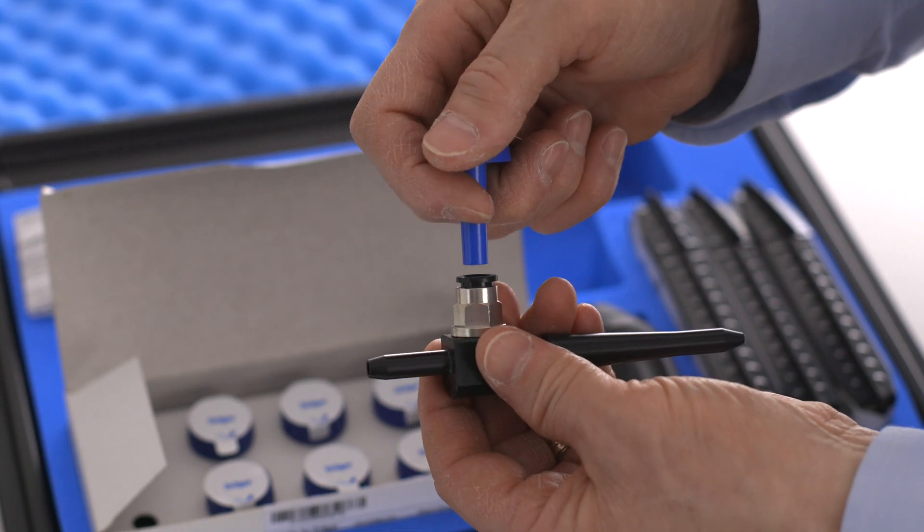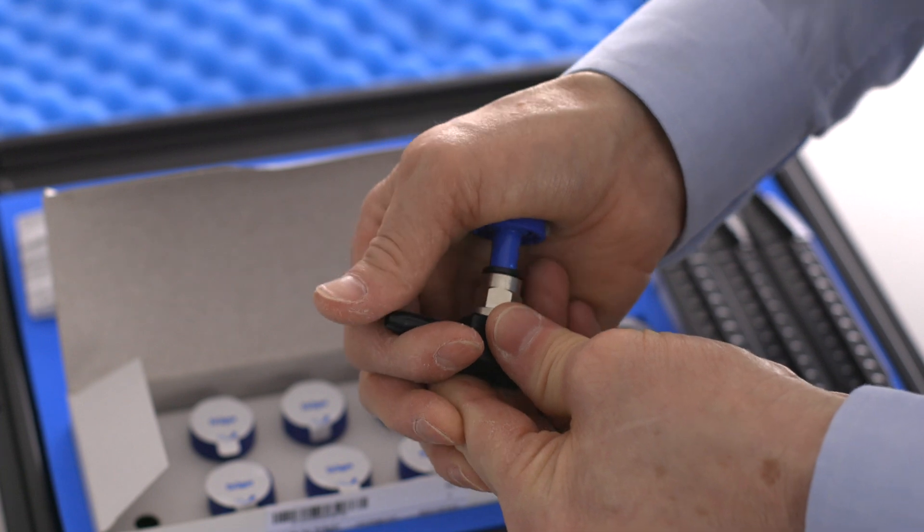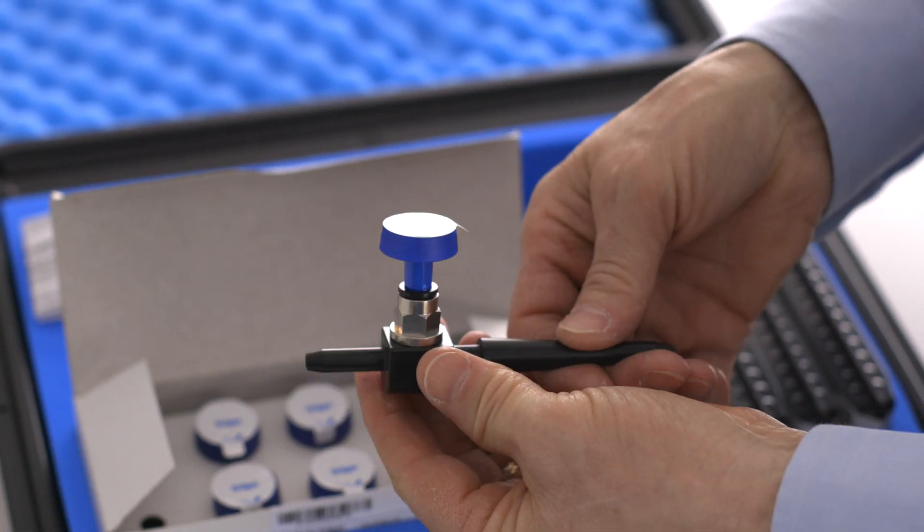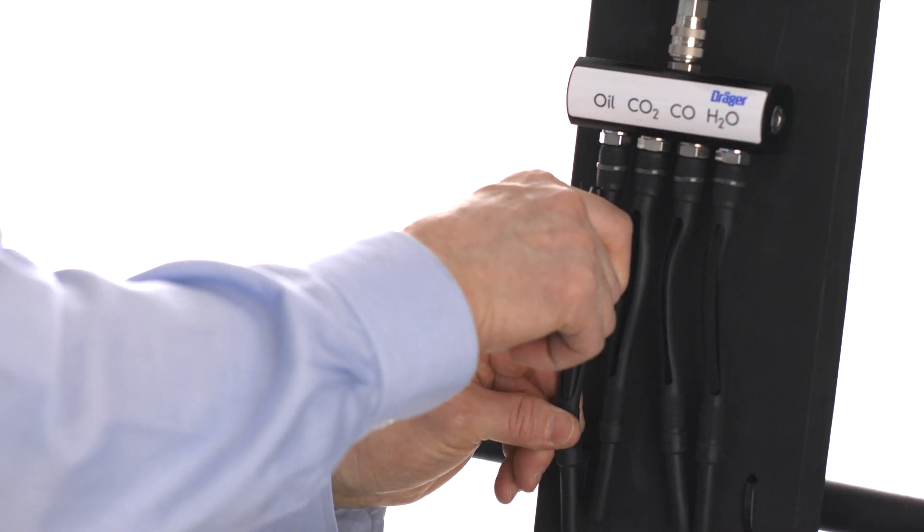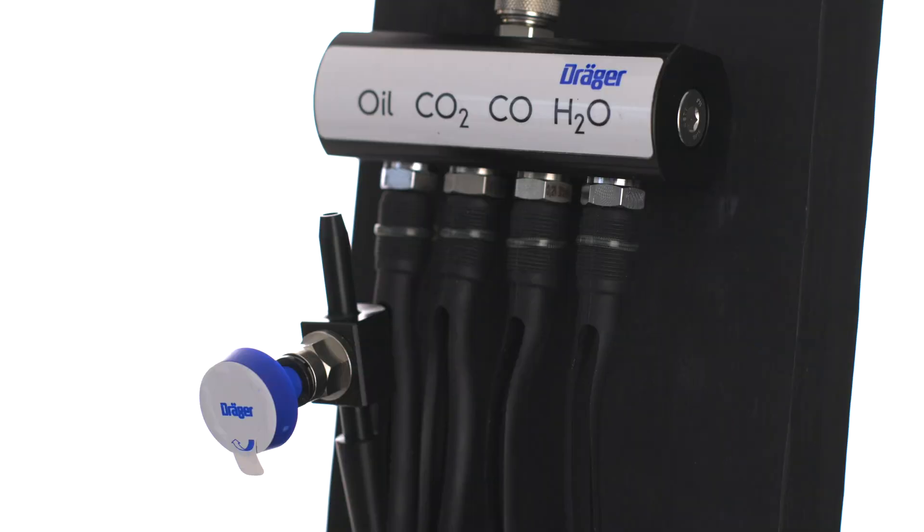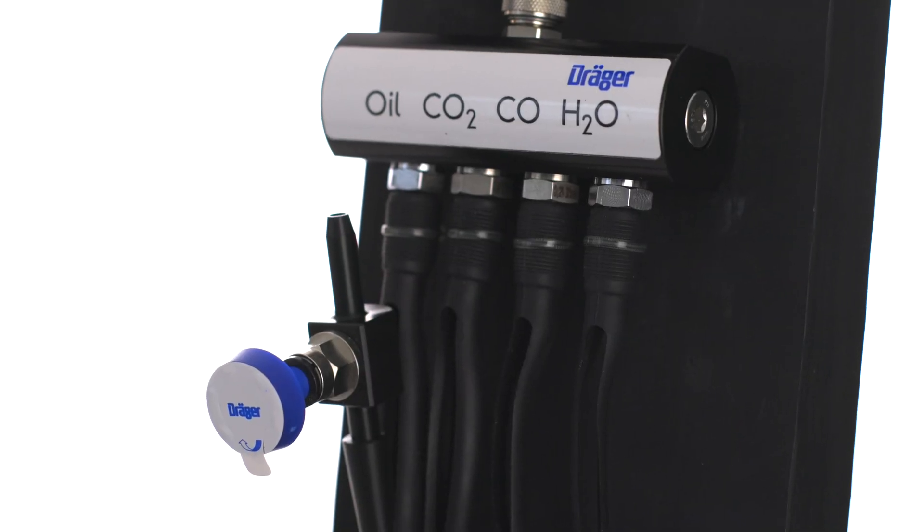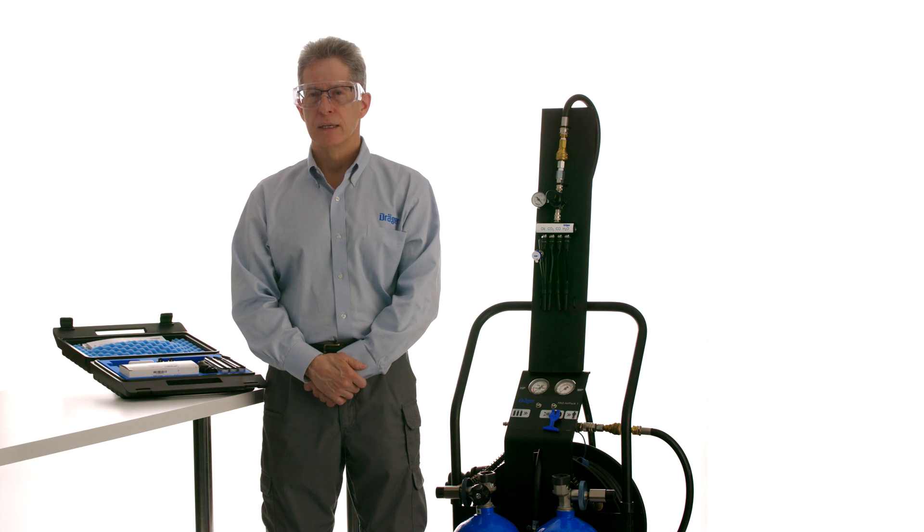Now we can start the pre-assembly of the impactor and the tubes. Attach an oil impactor to the impactor adapter. Insert the adapter into the bottom of the holder designated for oil. Leave the top part disconnected for now. Drager replaced the oil tube with the oil impactor some years ago because the impactor displays mineral oils and synthetic oils independent of the oil type or viscosity.